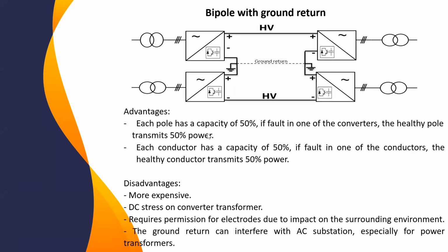So the advantage is the same, we have 50% for each pole. In case of any problem for one pole or one conductor, we still can transmit 50% of the power. The disadvantage here, we can see it is still more expensive. There is still DC stress in the transformer.